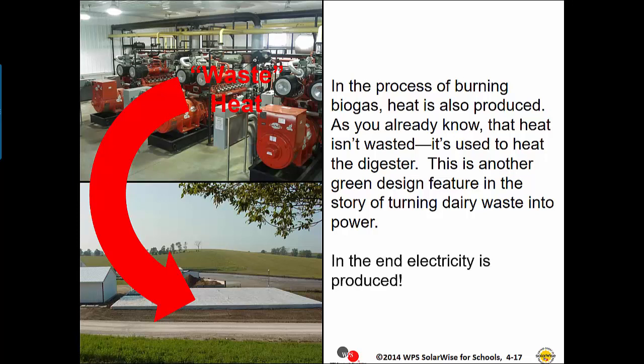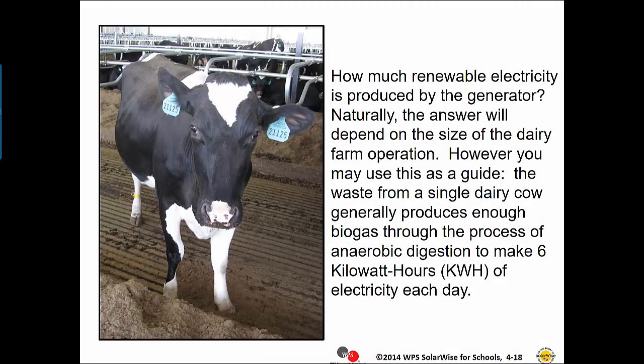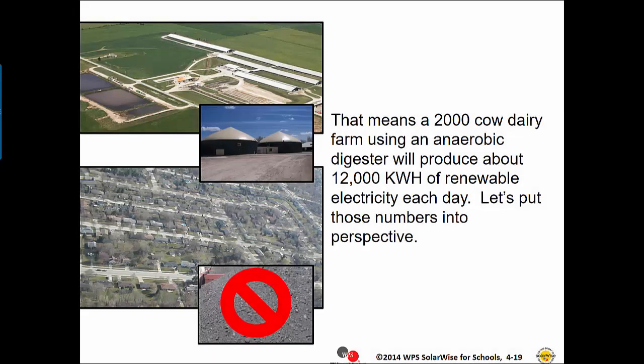In the end, electricity is produced. How much renewable electricity is produced by the generator? Naturally, the answer will depend on the size of the dairy farm operation. However, you may use this as a guide: the waste from a single dairy cow generally produces enough biogas through the process of anaerobic digestion to make six kilowatt hours of electricity each day. That means a 2,000 cow dairy farm using an anaerobic digester will produce about 12,000 kilowatt hours of renewable electricity each day.